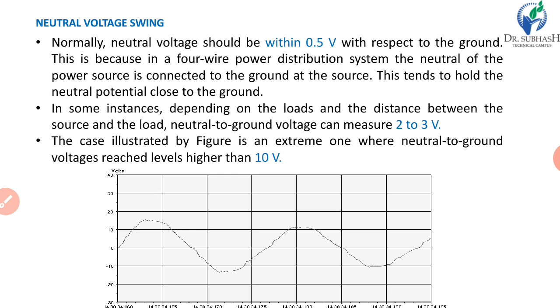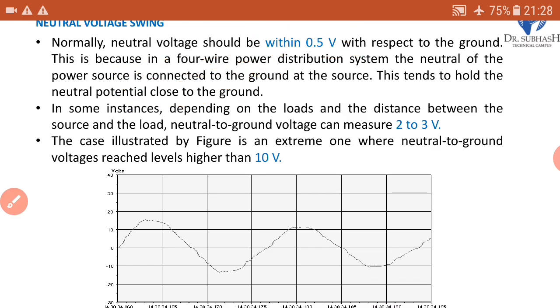Neutral voltage swing. Normally, neutral voltage should be within 0.5 volt with respect to ground. This is because in a 4-wire power distribution system, the neutral of the power source is connected to the ground at the source. This tends to hold the neutral potential close to ground. In some instances, depending on the loads and the distance between the source and the load, neutral to ground voltage can measure 2 to 3 volts. The case illustrated by the figure is an extreme one where neutral to ground voltage reaches levels higher than 10 volts. So it is a very extreme case, because the normal level should be within 0.5 volt, and here there is greater than 10 volts. So this is a very extreme condition and it may be generated.